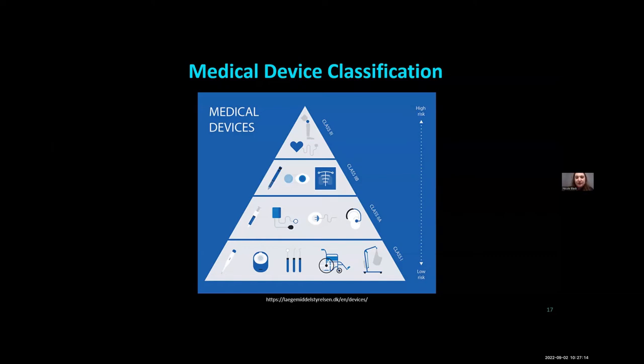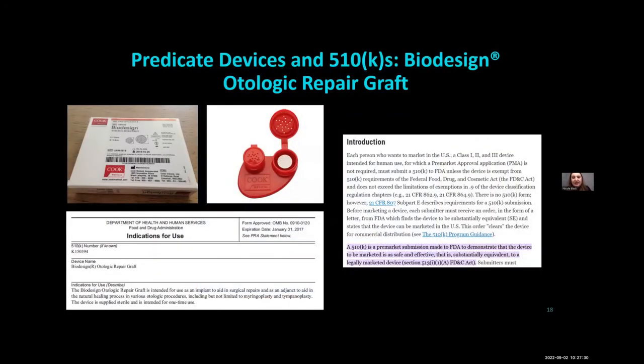One of the first things you have to do when designing a medical device is decide which class it fits into, because that determines the pathway you follow. If you have a class two device, you can go down the pathway called 510(k) clearance, which requires identifying what other devices are out there that could serve as a predicate device.